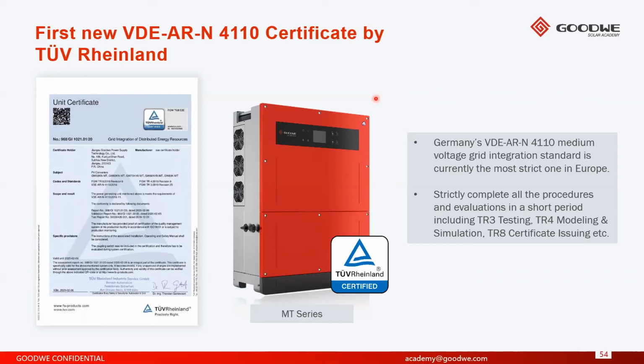The inverters go through a very robust and intense testing process, which usually takes up to 2 to 3 months. And the cost of having a certification like this is anywhere between 15,000 to 30,000 euros. So as you can see, there's quite a large commitment that's been made by GoodWe to have our inverters certified for this particular standard.